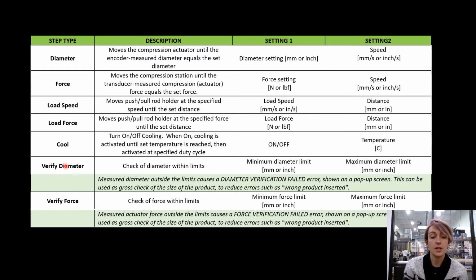The next two step types are the verify force and verify diameter. These are simply check steps that allow you to set a minimum and a maximum limit range on either your diameter or your force, and the machine will check to verify that the crimped state of your stent is within either that diameter or that force range. If it fails, it will give you a warning to let you know that your stent is not within your limited range.